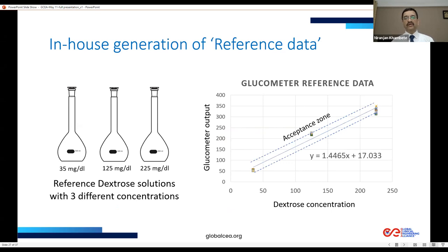He can immediately check the glucometer to find out whether the device and strips are good, or whether the user wasn't using it correctly. If the glucometer and strips are good, the readings will fall within the plus or minus two standard deviation band shown here. One has to really apply their mind to ensure the quality of equipment remains good while it is in clinical use.